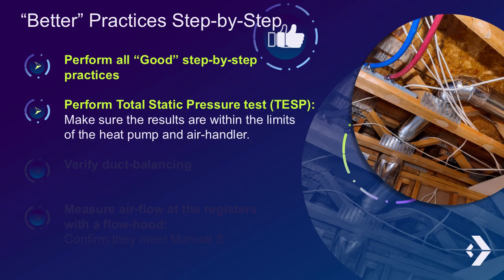Everything from the good steps still applies, but now we're adding diagnostic tests to ensure the system performs better. Start by performing a total static pressure test, or TESP. This test measures how restrictive the duct system is and ensures the results are within the limits of the heat pump and air handler. You can test the system as is during the assessment phase, and you should also test it again during commissioning. While we won't teach the full protocol for TESP in this video, it's important to understand its value in diagnosing duct performance.